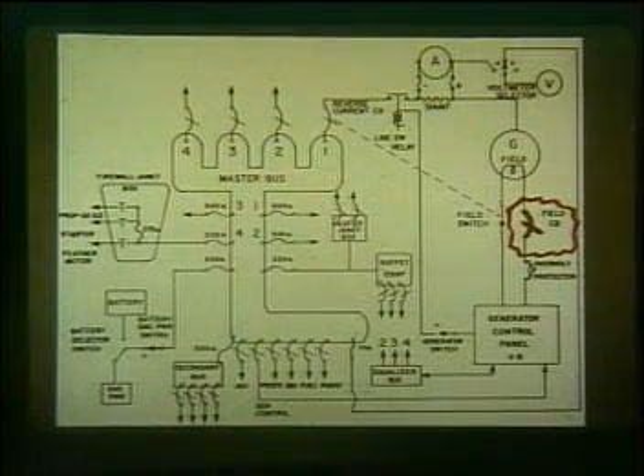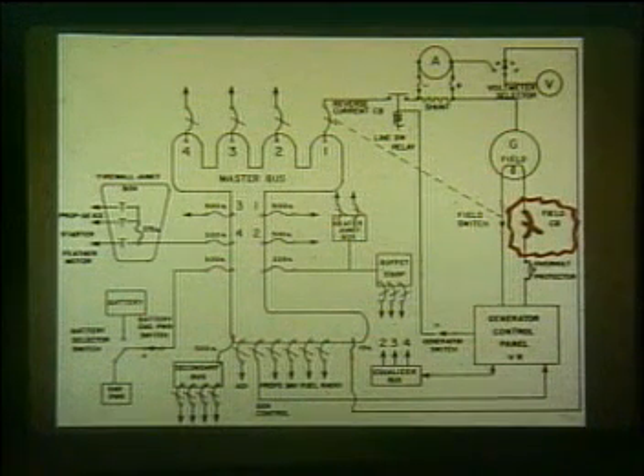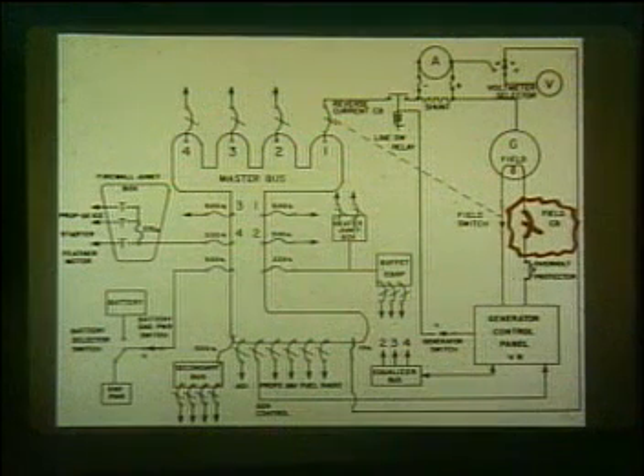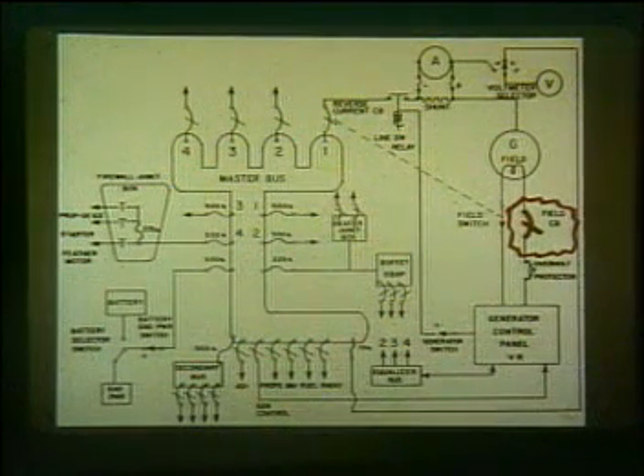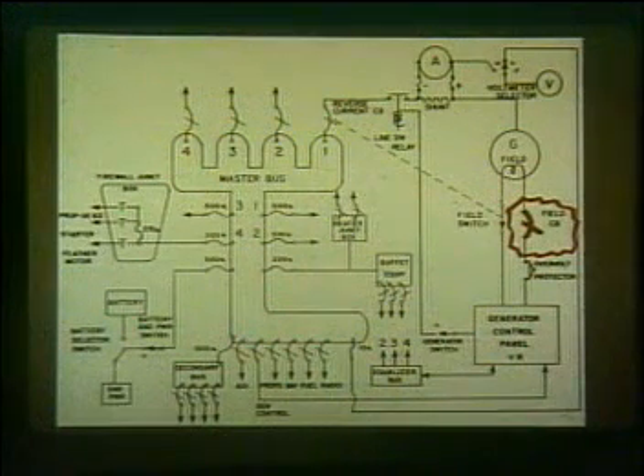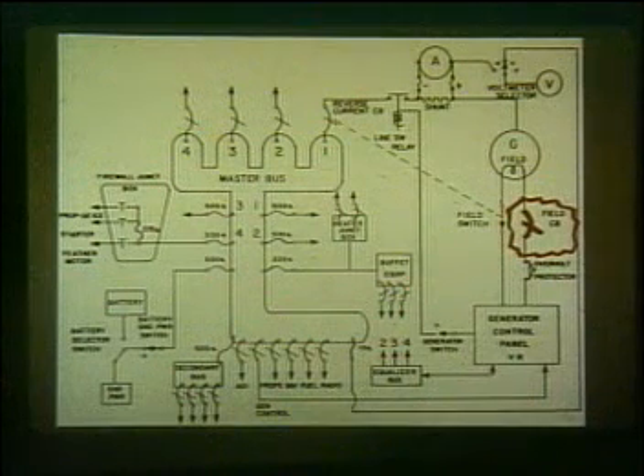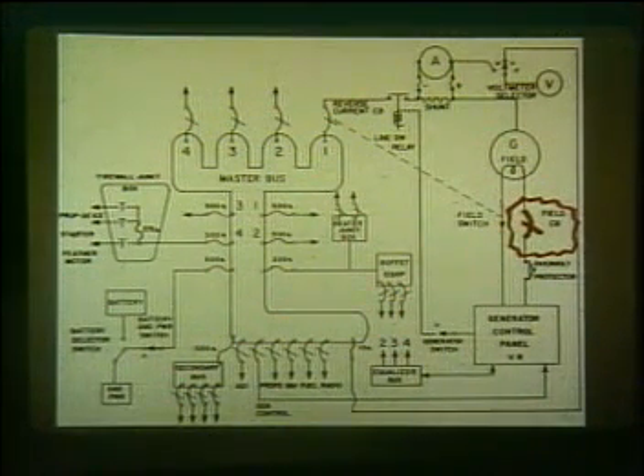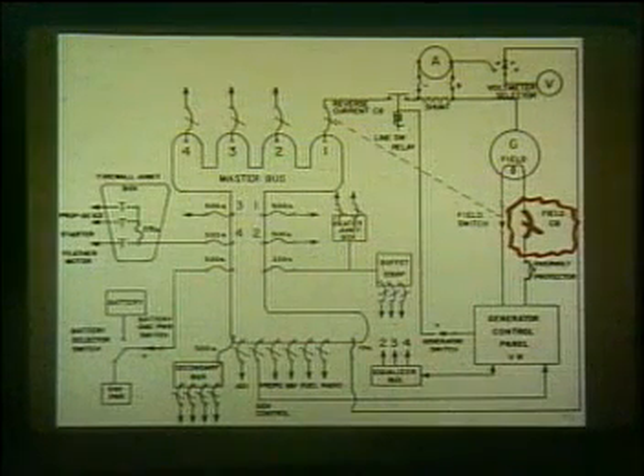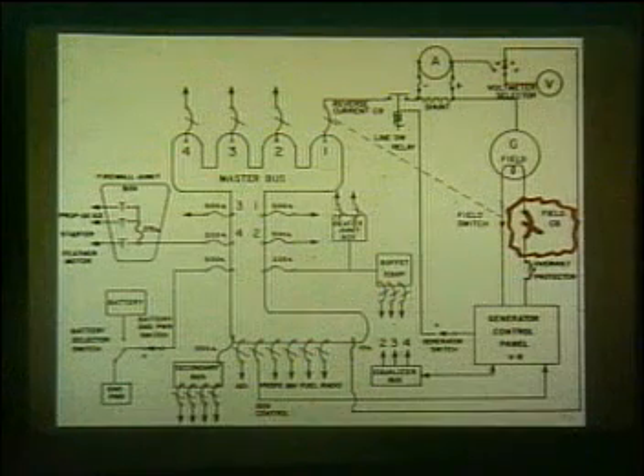The generator field circuit breaker is one of three protective devices in the generator field circuit. The field circuit breaker will protect the generator in the event of a heavy current flow through the field. This is the only protective device in the generator field that can be manually tripped to open the circuit. As illustrated by the previous slide, the reverse current circuit breaker will also open the field circuit through the field switch.